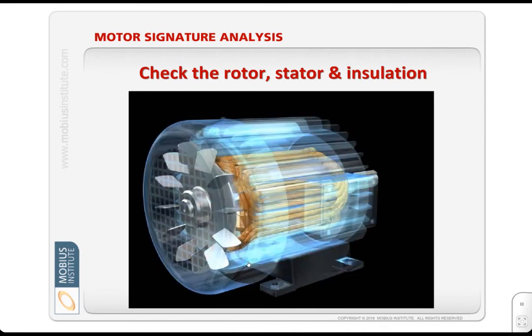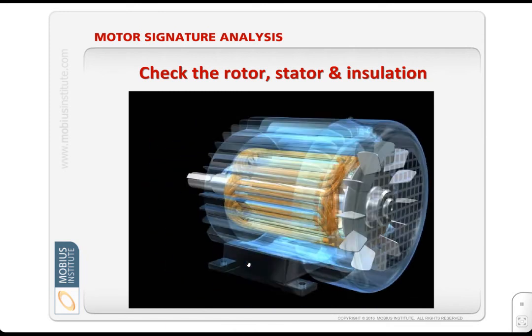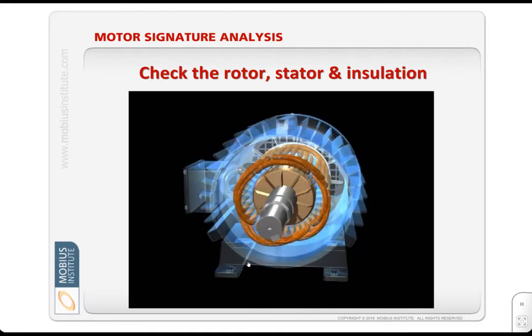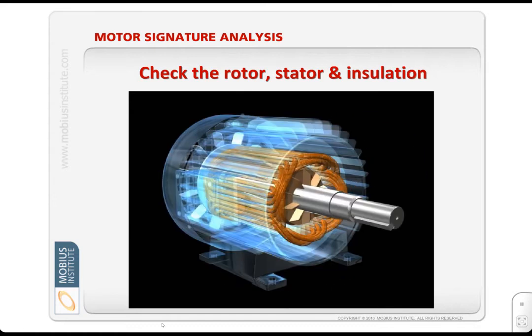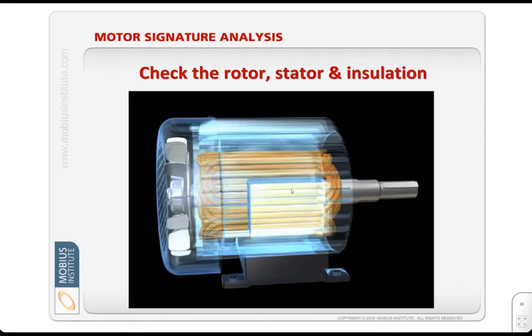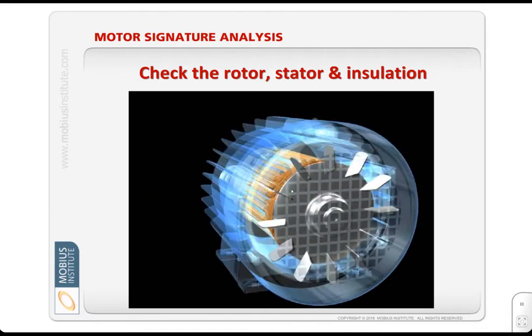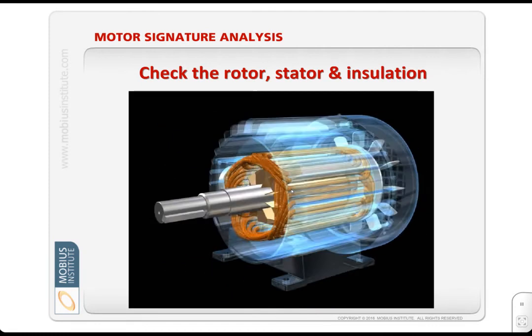With our electric motors, we can tell if there are supply problems to the motor, like voltage with harmonics. We can see imbalances in voltage across the three phases. We can see if there are problems with the connectors, with the stator, with the rotor, broken rotor bars, insulation issues. Boy, there are all sorts of tests we can perform on our critical and precious electric motors.